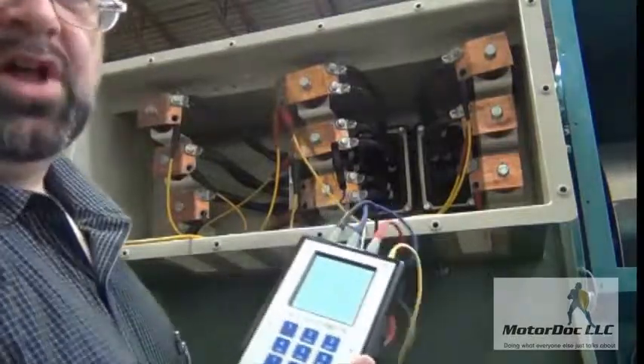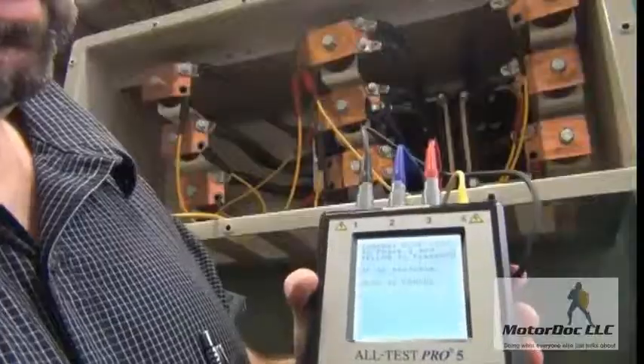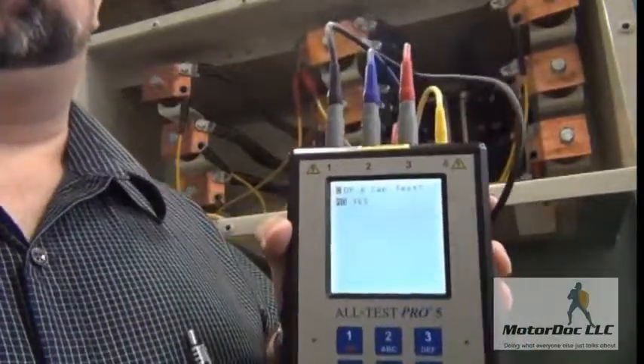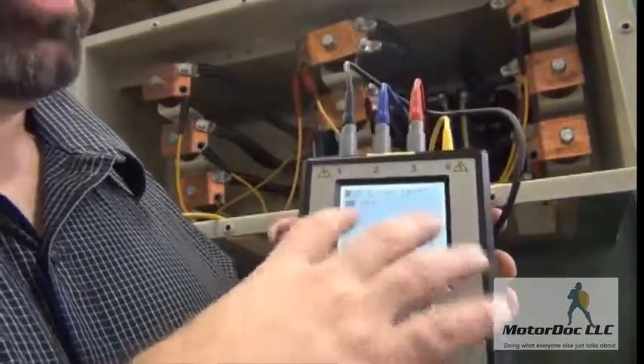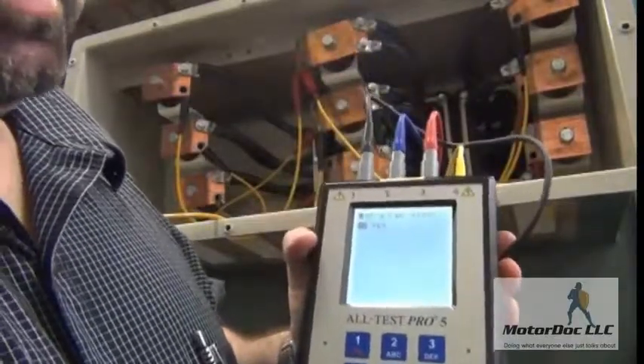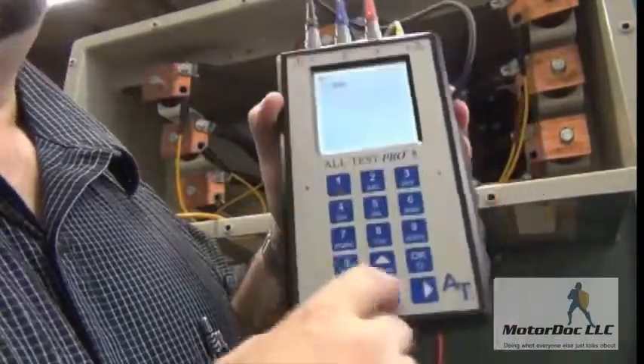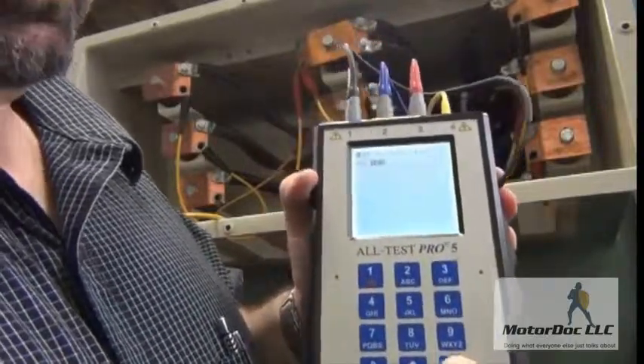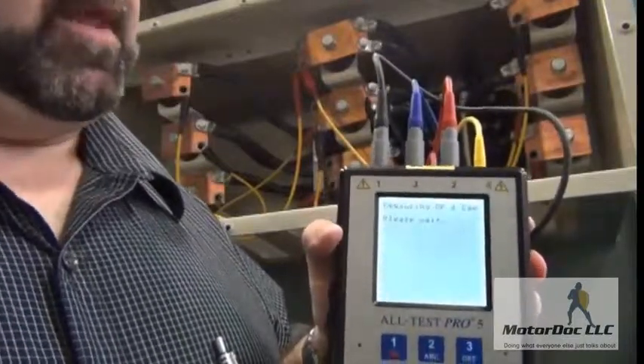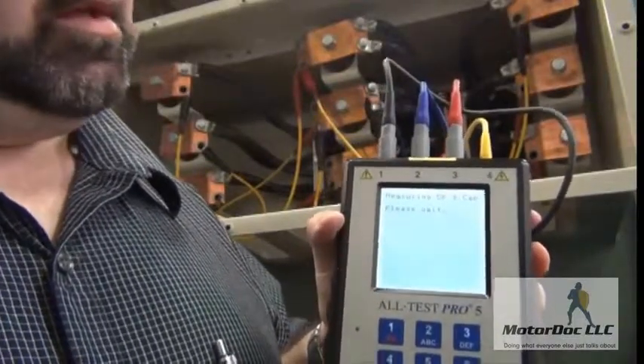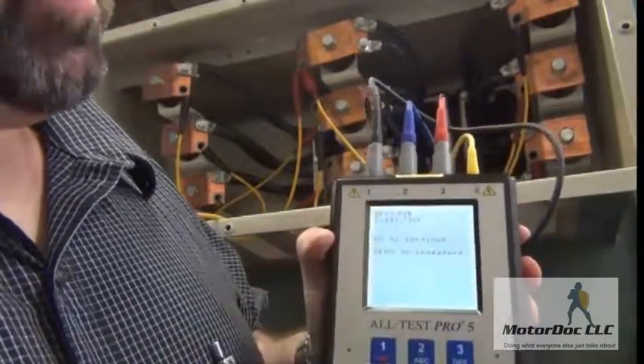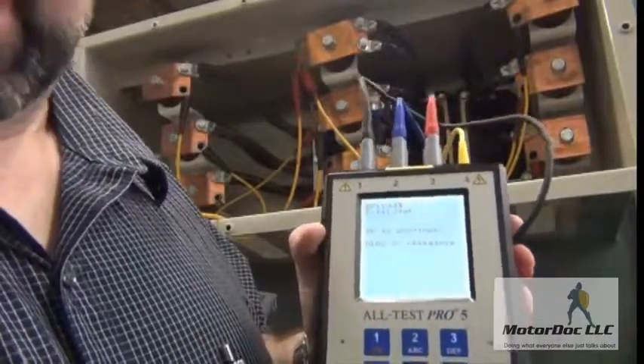Part of this will also check to make sure I have a good connection. I press OK. Then it asks if I want to do a dissipation factor and capacitance to ground test - I'll have that covered in another presentation. I select yes and click OK, allowing it to run those tests. It displays the dissipation factor and the capacitance of this circuit. Press OK to continue.